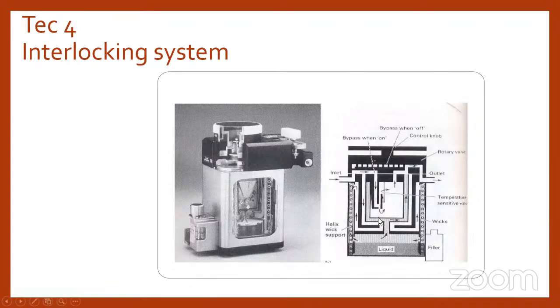And the major principle remains the same. It has an inlet. The air will be bypassed. Some percentage of fresh flow will enter into the vaporizing chamber. So bypass will come out of this pathway, and the vaporizer will come out of this pathway. Both of them will mix in the common outlet, and it will be delivered to the patient. It has a series of wicks to increase the surface area inside the vaporizing chamber, so more vapor is available for the fresh gas to be mixed with, and it has a filler at the right bottom. Whenever the anesthetic agent is exhausted, we can refill it with fillers.